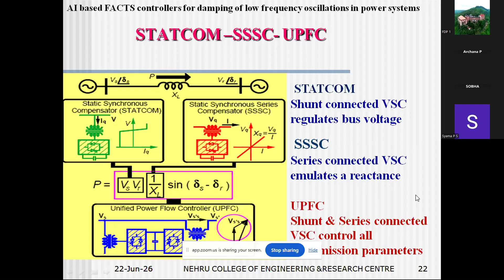So it's a shunt and series connected VSC technology. Using this, it is possible to control voltage, impedance, and even the phase angle. That is the beauty of a unified power flow controller. This was proposed by Gyugyi in 1991, and it can simultaneously or selectively control all parameters affecting power flow in the transmission line: voltage, impedance, phase angle. This unique capability allows it to independently control real and reactive power flow in the line. That is UPFC, Unified Power Flow Controller.